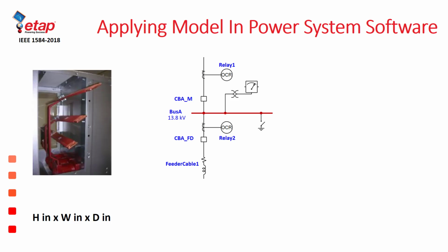Another area which was typically confused is the actual bus compartment. So far, we have been looking only at the access through the front end of the equipment. However, as we all know, there may be tasks which involve inspecting the equipment from the sides or the back if we have rear access to the equipment. Under those conditions, there may be situations where the bus could be modeled as a separate compartment of different sizes and, of course, with potential electrode configurations which may even involve the HCB configuration, as shown in this image.